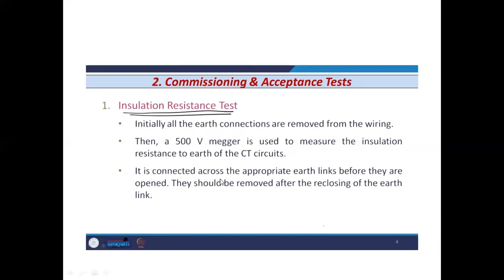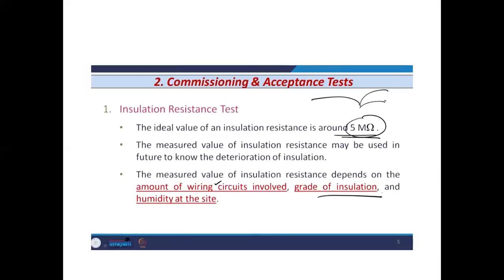It is connected across the appropriate earth links before they are opened. The connections should be removed after the reclosing of the earthing. The ideal value of the insulation resistance is around 5 megaohms. This is a huge amount, and the insulation level should be as high as possible.